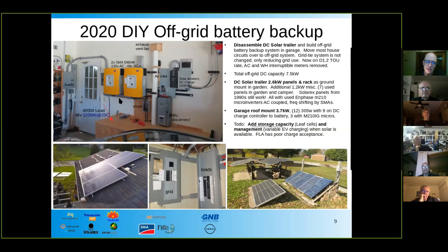The AC wiring comes through this conduit into a loads panel in the garage, then conduit runs down through the basement to the opposite corner to the original grid panel that was in the house. I added a new loads panel next to it and moved most of the circuits into it. Some circuits that were already at this end of the house near the garage got rerouted into this panel to free up space down in the basement, so now there's extra room down here.